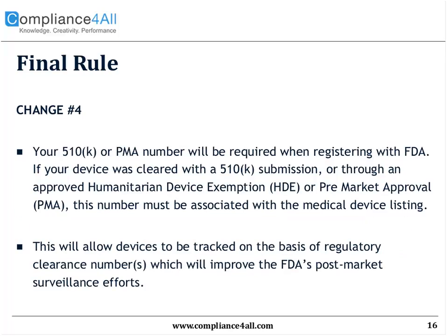Another significant change based on the final rule, change number four: your 510(k) or PMA number will be required when registering with FDA. If your device was cleared with a 510(k) submission, also known as a pre-market notification, or through an approved humanitarian device exemption, also known as the HDE, or a PMA, pre-market approval, this number must be associated with the device listing under the new final rule requirements. This will allow devices to be tracked on the basis of regulatory clearance numbers, which will certainly improve the FDA's post-market surveillance efforts.